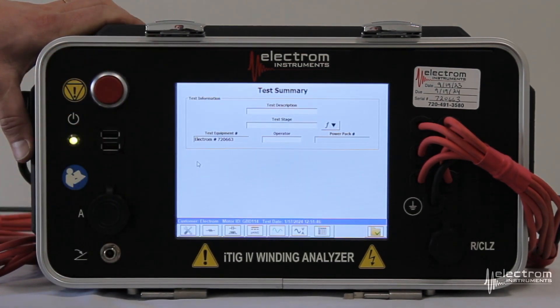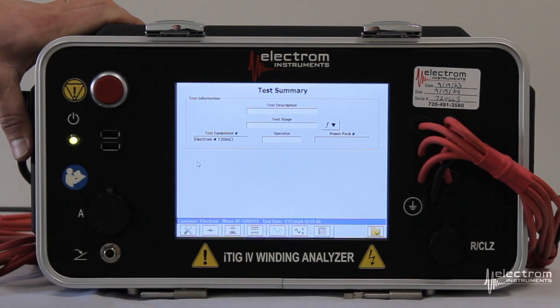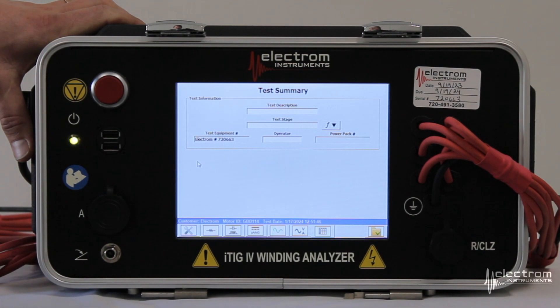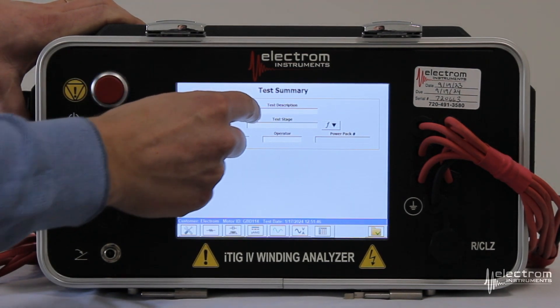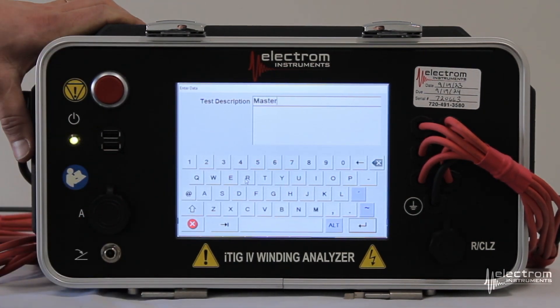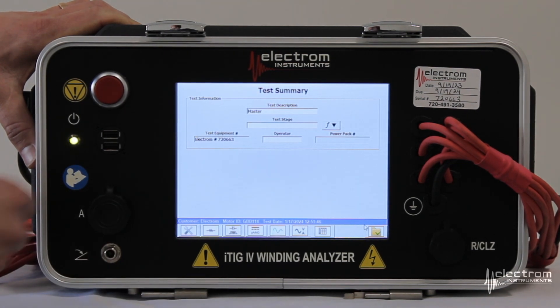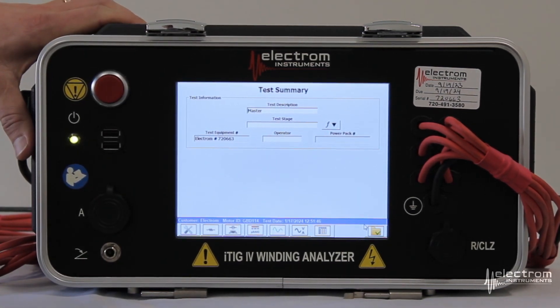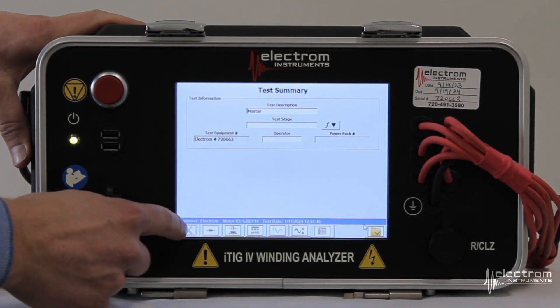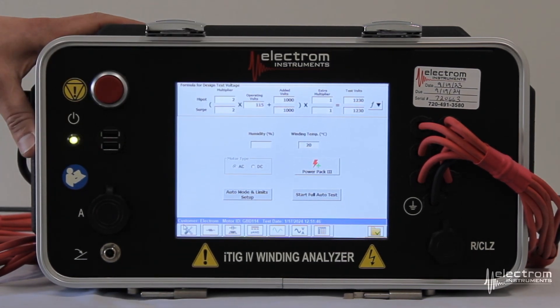Working left to right as usual, we're on the test summary screen. Here we can enter in a few more pieces of information in the test description field. In this case I'm going to enter in 'master' to define in our database that this will be the test set used as our master or reference. We can also enter in a test agent or operator if that's helpful for your reporting purposes. Next, we go to the setup screen where we see our high pot and surge test voltage formulas. The white fields can be changed or the test voltage itself can be overridden in the column on the far right.